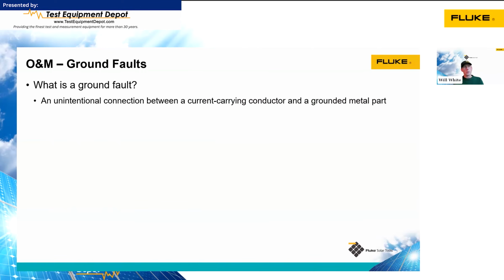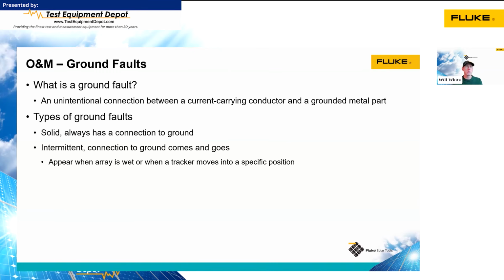Let's talk about ground faults. A ground fault is an unintentional connection between a current carrying conductor and a grounded metal part. So this is our positive or negative on the DC side has come into contact with something like the module frame or the racking. So we're losing energy out to the ground. There are two main types of ground faults: a solid ground fault where it's always making contact, and an intermittent ground fault that comes and goes.